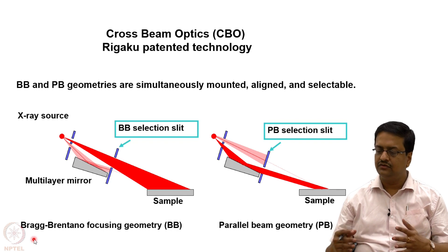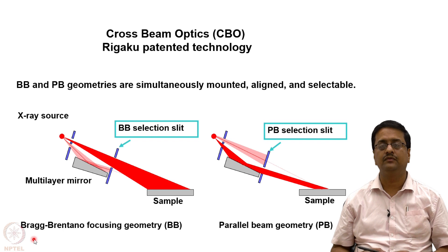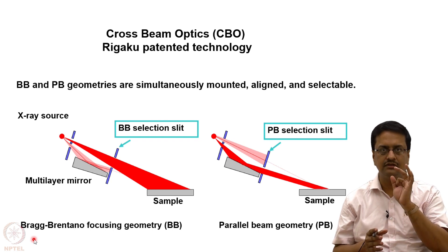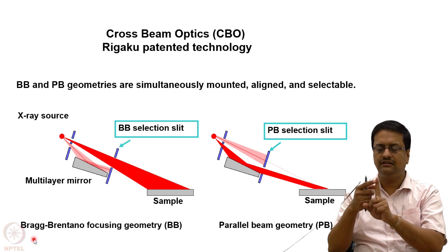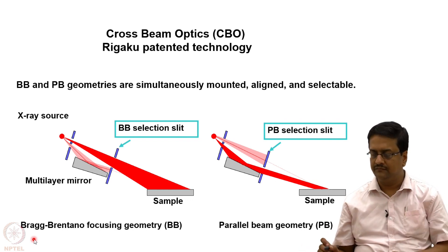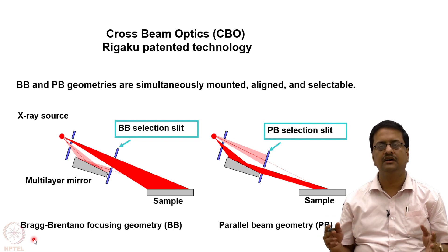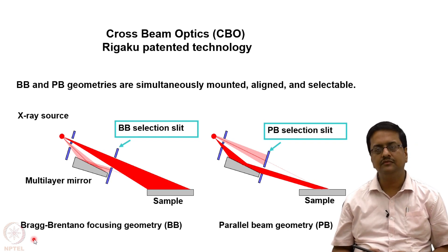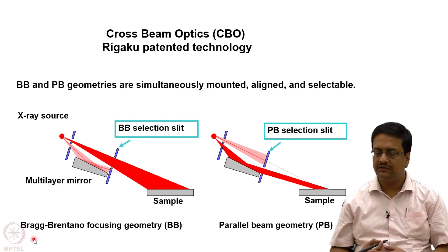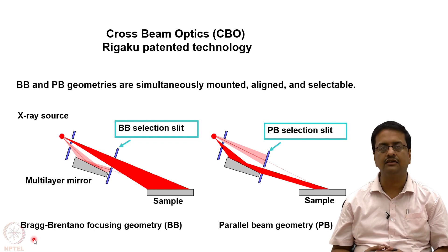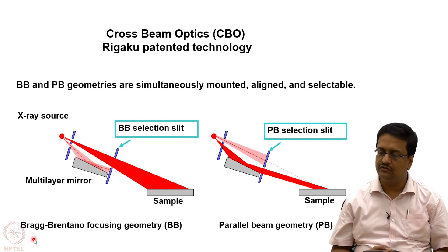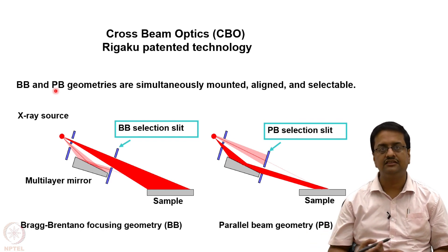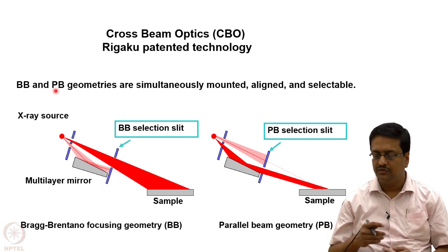For powder diffraction, we use a line focus beam rather than a circular focus beam, where the line falls on the sample. The beam can be divergent or parallel. This schematic shows the cross beam optics, a patented technology by Rigaku Corporation — now Rigaku Oxford Diffraction. The Bragg-Brentano (BB) and parallel beam (PB) geometries are simultaneously mounted, aligned, and selectable by a change of slit.